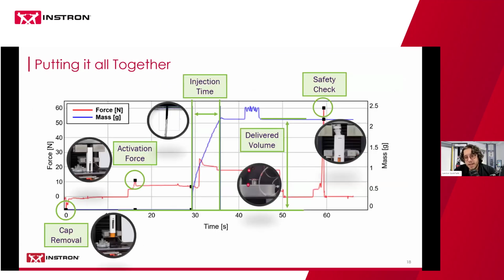So putting it all together, this is just an example curve that you could produce using this type of system, showing all of the key points. So doing cap removal, activating the device, triggering the activation. You have the mass in blue, the forces in red. You have the mass profile over time, you have the scale capturing the delivered volume, and then you typically do a safety check of the device.